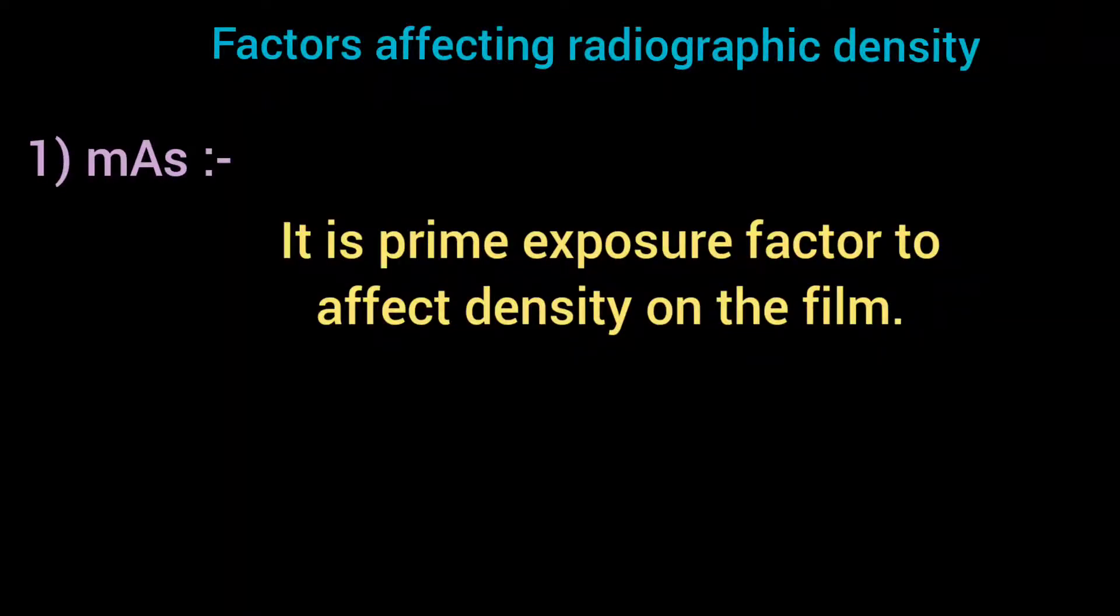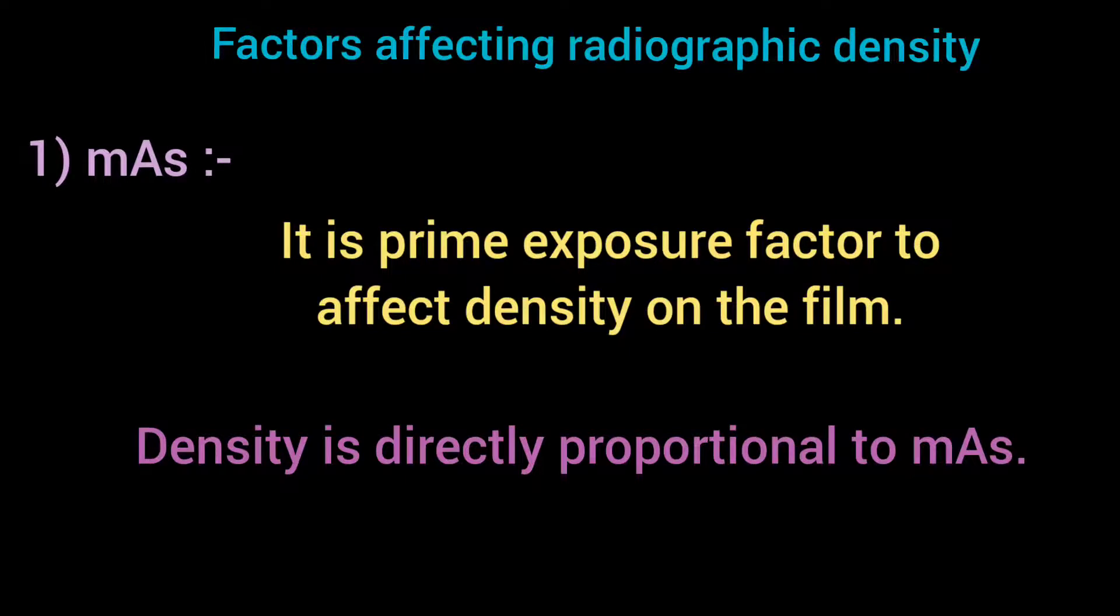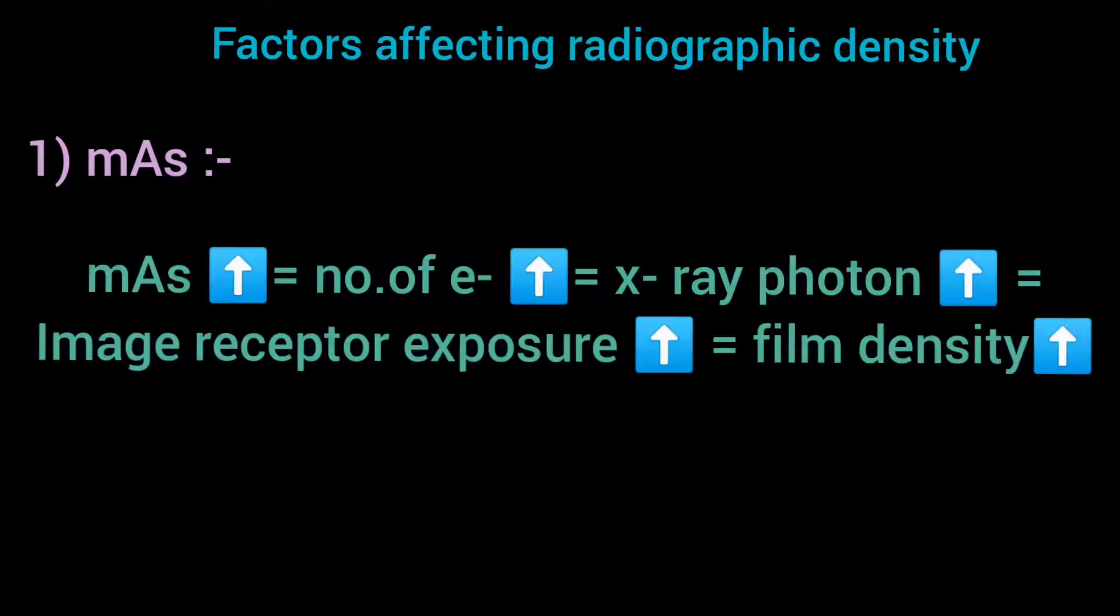The density on the film is measured by a device called densitometer. Factors affecting radiographic density: mAs is a prime exposure factor affecting radiographic density. Density is directly proportional to mAs. Increasing mAs increases the number of X-ray photons produced, which results in increased image receptor exposure and overall film density.